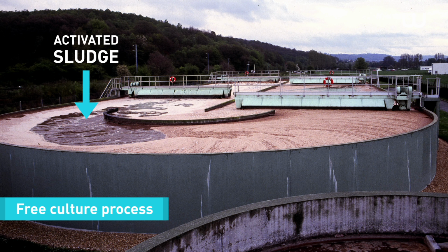For activated sludge, the development of the purifying biomass that evolves freely in a tank is maintained. This tank is fitted with a stirrer which keeps the culture in suspension. It is also fitted with an aeration system which enables it to maintain a sufficient level of oxygen essential for the development and the activity of microorganisms in the biomass.